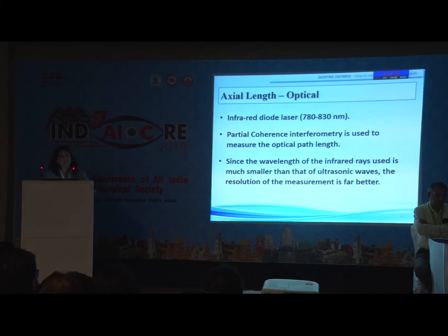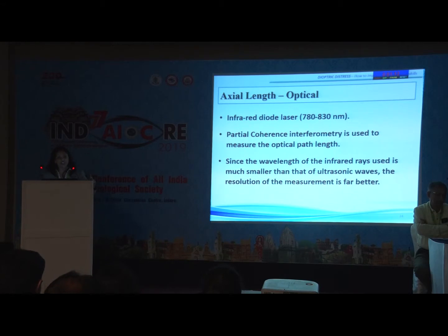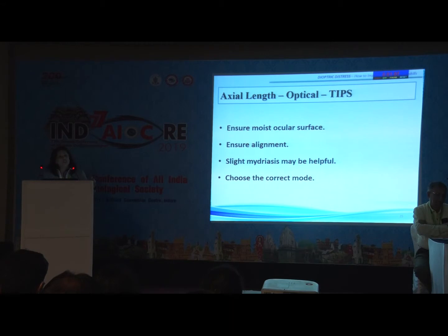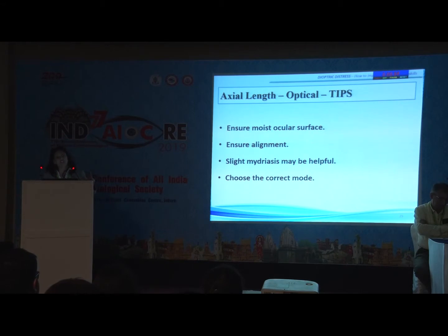Optical biometry is a better instrument overall, but it does not work in all cases. It is based on the principle of partial coherence interferometry, and the resolution is better because the wavelength of infrared rays is much smaller than that of ultrasonic waves. While performing optical measurements, ensure a moist ocular surface to get accurate readings and ensure axial alignment. A slight mydriasis may be helpful in cases of slight — but not dense — posterior subcapsular cataract. Dense PSC may prevent the instrument from obtaining readings. Choose the correct mode.